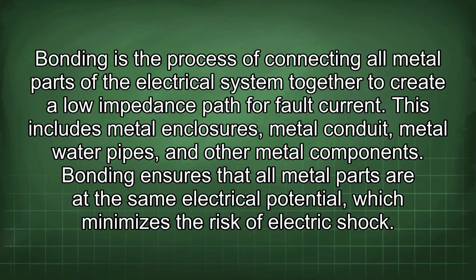Bonding is the process of connecting all metal parts of the electrical system together to create a low impedance path for fault current. This includes metal enclosures, metal conduit, metal water pipes, and other metal components. Bonding ensures that all metal parts are at the same electrical potential, which minimizes the risk of electric shock.